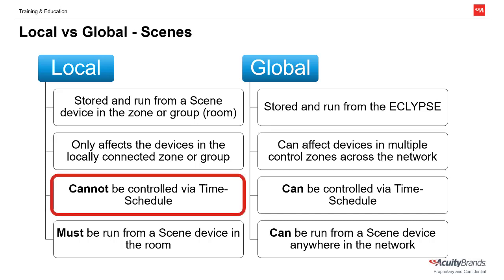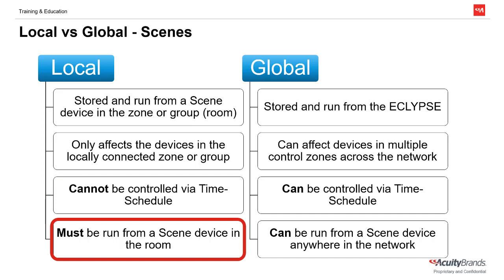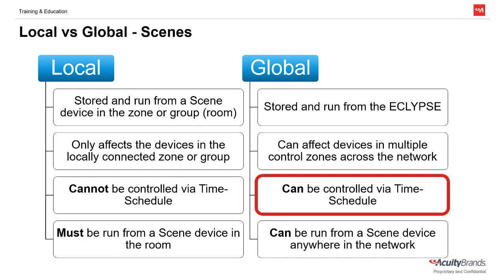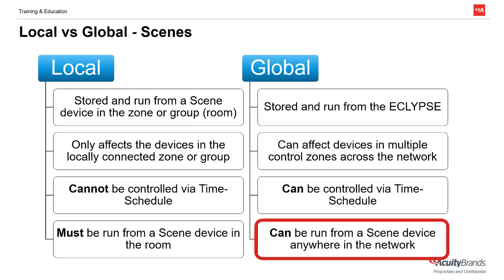Local scenes cannot be controlled by a time schedule — they must be run from a scene controller in the room. But conversely, global scenes can be controlled by a time schedule, and can also be run on demand from a scene controller device installed anywhere on the network. Note that you must have a fully networked system with bridges and an Eclipse in order to utilize global profiles and presets. Standalone rooms and zones can only use local scenes.